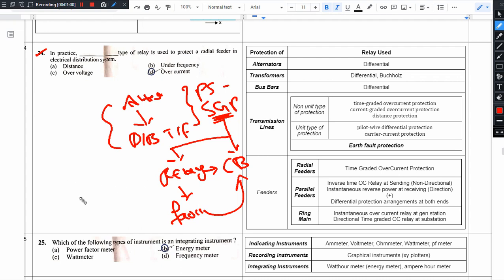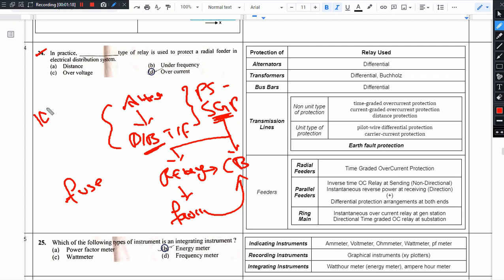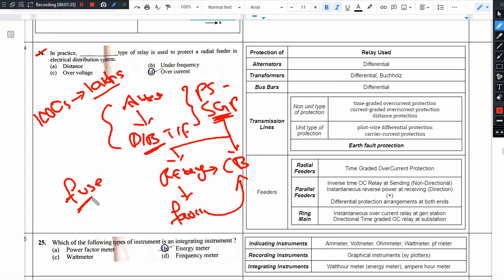We can use circuit breakers, and the fuse arrangement is also done here — where the circuit breaker is a costly affair, we can use fuse protection. For distribution transformers, the circuit breaker is unnecessarily costly. Because in a distribution network there are thousands of distribution transformers, so for each one we can't install a circuit breaker. That's why we have a fusing arrangement for distribution transformers.